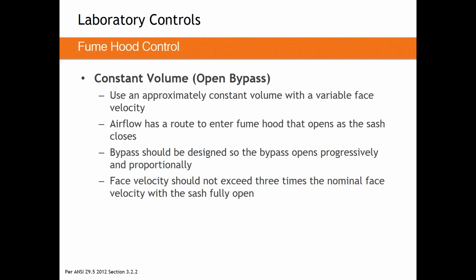There are about 750,000 fume hoods in the United States. About 1/3 of those are constant volume. Now that number is debatable, it is a bit of an estimate, but the point is constant volume fume hoods are not an old technology. They are still a viable fume hood to use and a good design to use sometimes, but they're not always applicable. A constant volume fume hood maintains an approximately constant volume, but the sash of these hoods can move. So the containment's pretty good on a device like this.